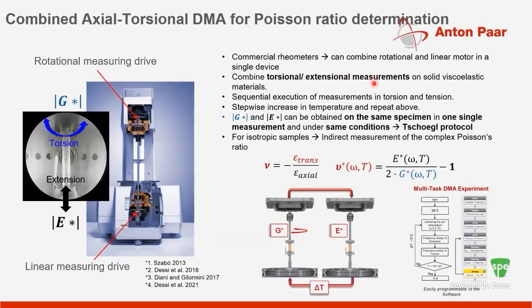What I mean by this is that you're using two different actuators. You can see one actuator is the rotational drive, which we have spoken a lot about today, and which allows you to do measurements in torsion, where you're shearing the sample. So you get something called a G star, or the shear modulus. And then you have another actuator which applies axial deformations. It could be in static or dynamic conditions. And if you do it in dynamic conditions, or in an oscillatory type flow in the axial mode, you basically get an extensional type measurement. So you can get both G and E type data on your samples. And now you can actually get this data on the same sample, the same specimen, in a single measurement under the same environmental conditions.